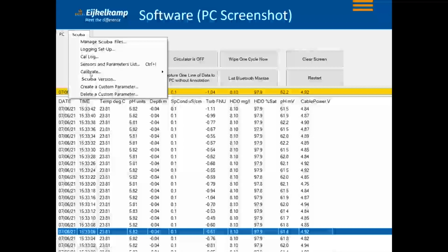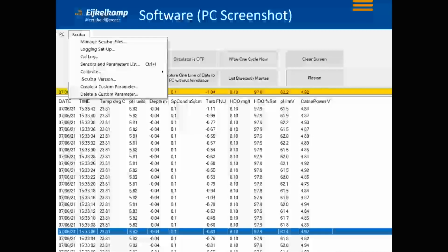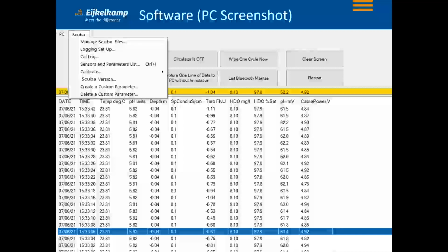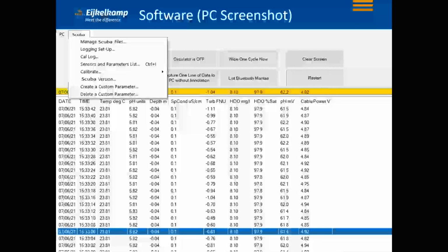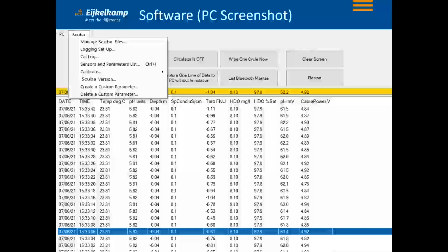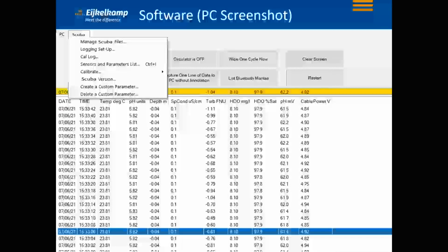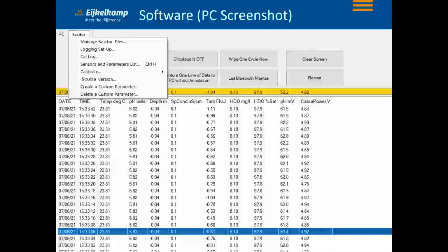The calibrate option is, of course, for calibrating all the sensors. It's easy, and during calibration you get a graphic showing the result and the stabilization of the sensor. You can put in your calibration value of the standard calibration fluid, and also set up the first and second point, for instance for pH, where you have to calibrate on pH 7 and pH 4, or pH 10.